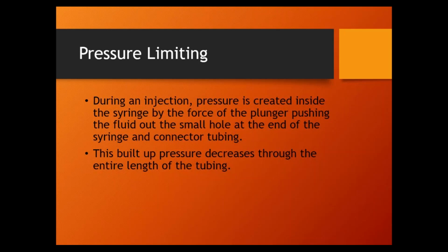You guys saw the difference between a 1 milliliter per second flow rate and a 20 milliliter per second flow rate. The primary determinant of how much pressure is in the syringe is the flow rate. The higher the flow rate, the greater the pressure built up in the syringe. Is the length and diameter of the tube also a factor? Yeah, but like I said, the main thing that affects how much pressure is built up in the syringe during the injection is the flow rate. That has by far the biggest effect.